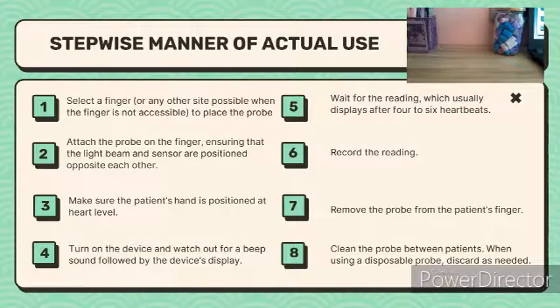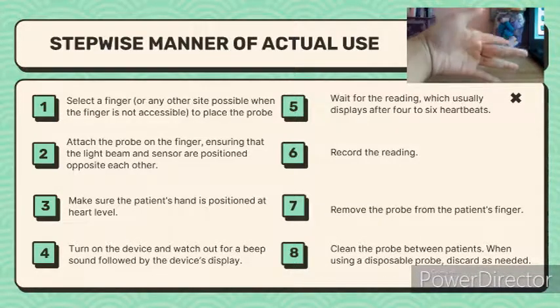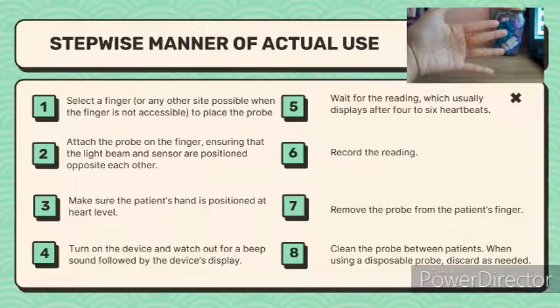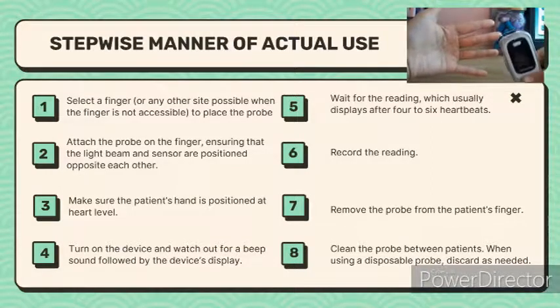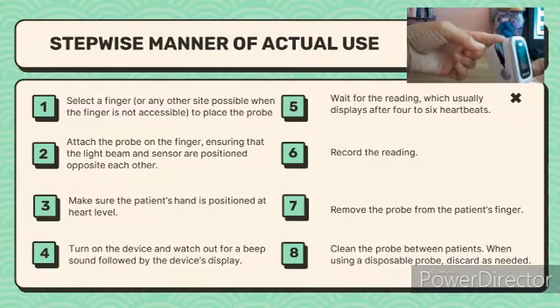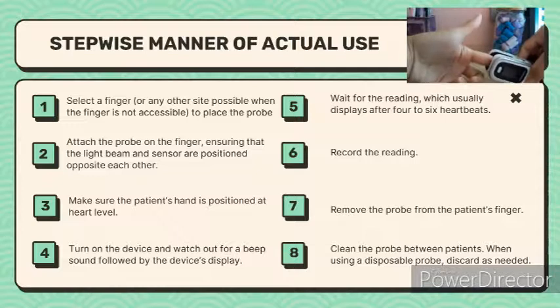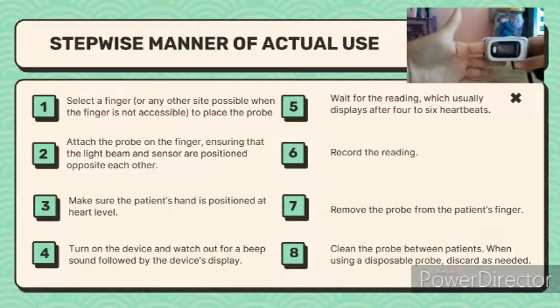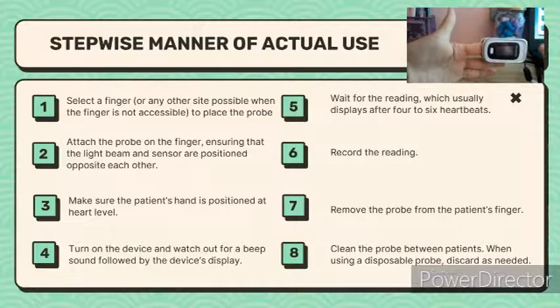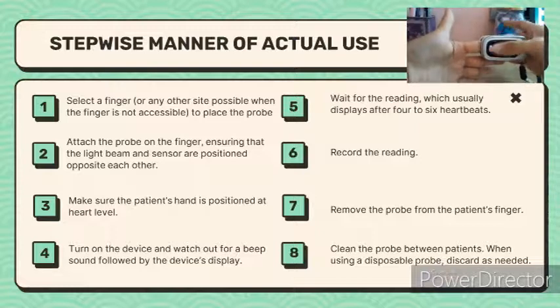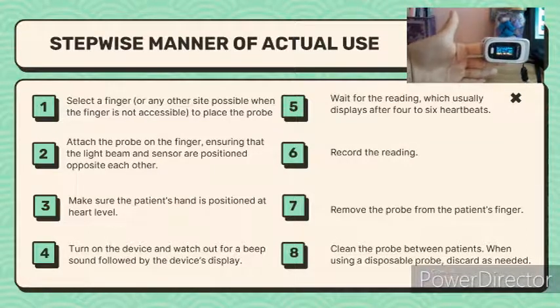Here is the stepwise manner of the actual use of the pulse oximeter. Firstly, select the finger, or any other possible site when the finger is not accessible, to place the probe. Attach the probe on the finger, ensuring that the light beam and the sensor are positioned opposite each other. Make sure that the patient's hand is positioned at heart level. Turn on the device and watch out for a beep sound followed by the device's display. Wait for the reading, which usually displays after 4 to 6 heartbeats.